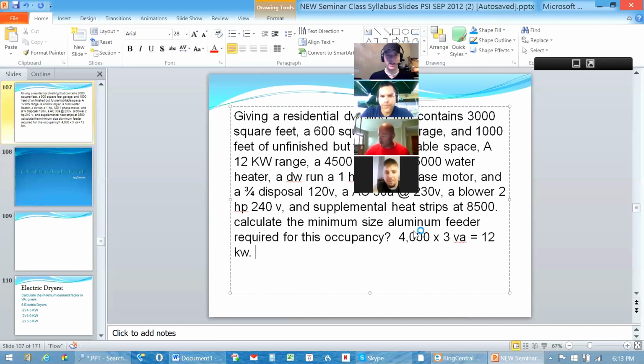Okay. So 12 kW is what we'll have for the lights and the plugs. That's all the 15 amp plugs everywhere in the house. Now, there's a few code requirements we have to include for the 20 amp, 125 volt required circuits, and those are the two kitchen circuits. All of this comes out of 220.52 A and B. Take a quick moment to flip over there and highlight it. It's a 1,500 VA value for each one that's required by 210.11(C). 220.53 is the section that has the requirements there.